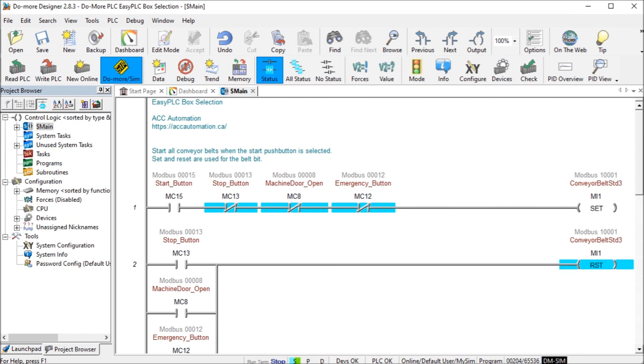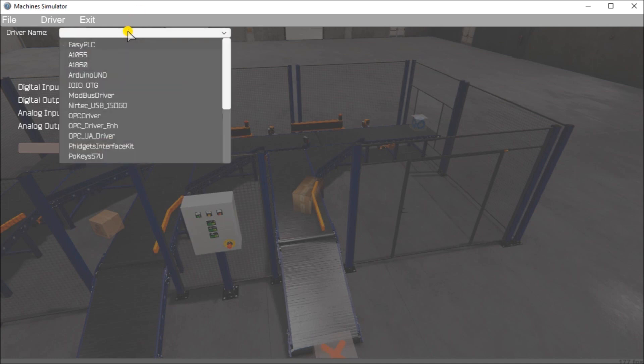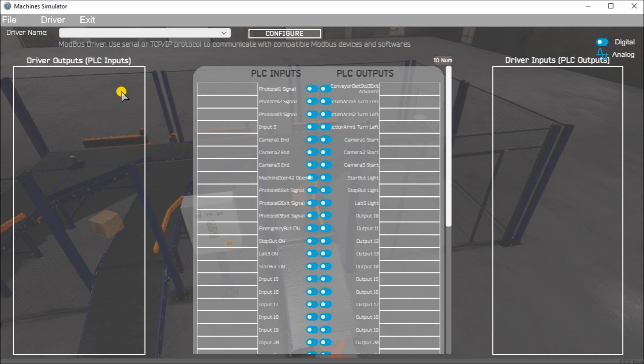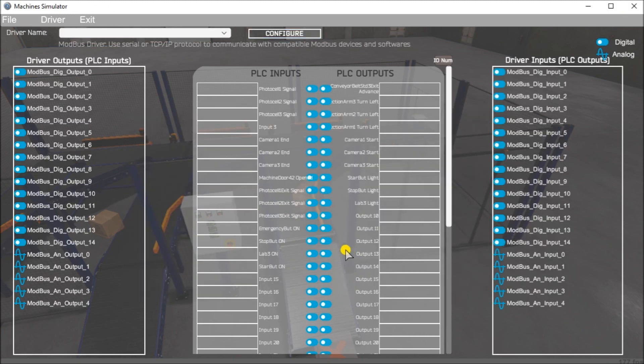Going back to our machine, we'll call up our driver and select Modbus. This is part of the final step: testing the program. We configure the Modbus driver with address 192.168.1.29, port 502 which is the default for Modbus, address zero, 15 digital inputs, 15 digital outputs, 5 analog in, and 5 analog out. Then we hit OK.